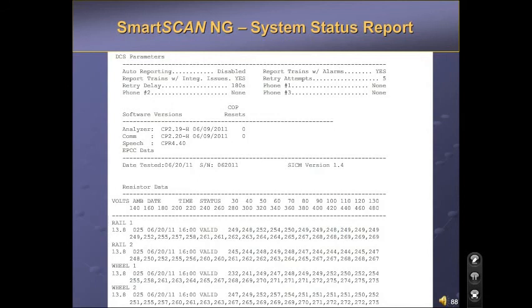The next area shows the current software versions in the NG system and the date tested and serial number of the EPCC board. The last section of the system status report is the integrity resistor tables. After calibration has been complete, the system will say resistor test beginning in 20 minutes. After the 20 minutes has elapsed, the shutter test will begin. The shutter will open and close for 480 seconds. After all the samples are gathered, they are populated in the resistor table.